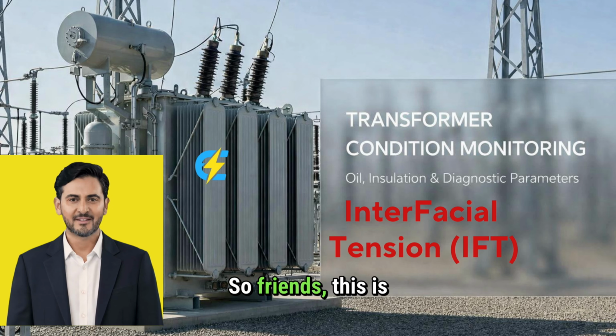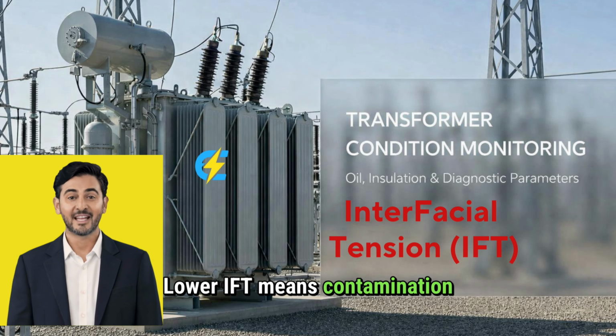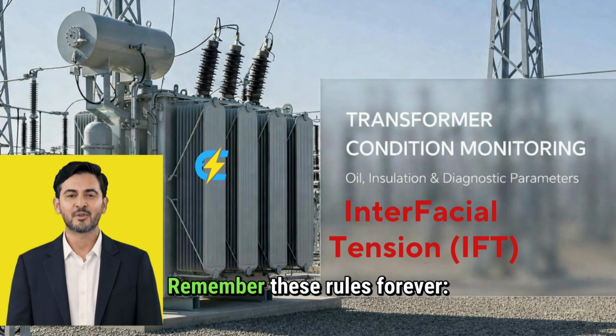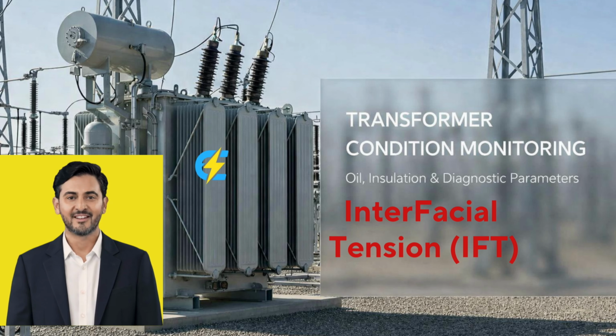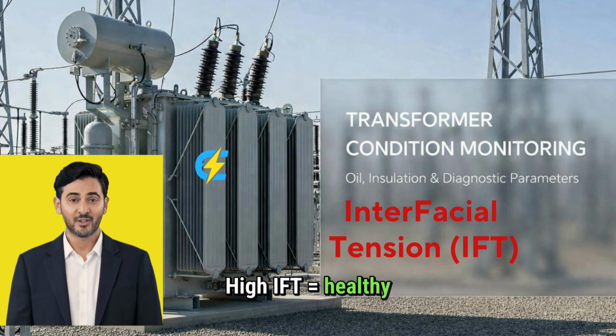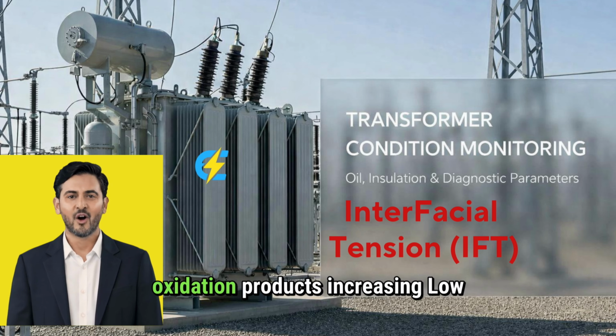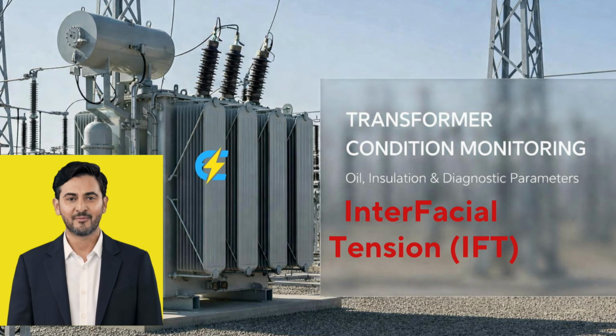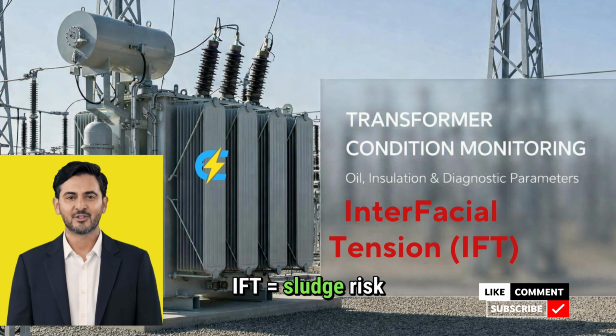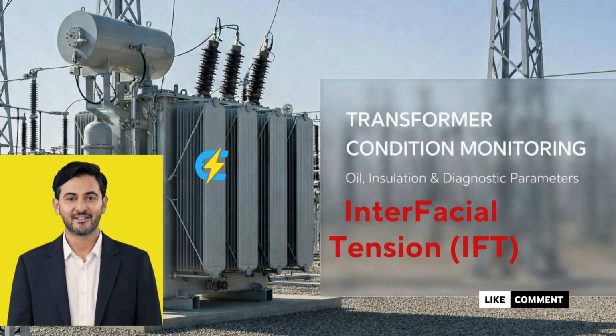So friends, this is the real meaning of IFT in transformer oil. IFT is a cleanliness indicator. Higher IFT means cleaner oil. Lower IFT means contamination is increasing. Remember these rules forever. High IFT, healthy oil. Falling IFT, oxidation products increasing. Low IFT, sludge risk and accelerated aging. IFT and TAN must always be read together.